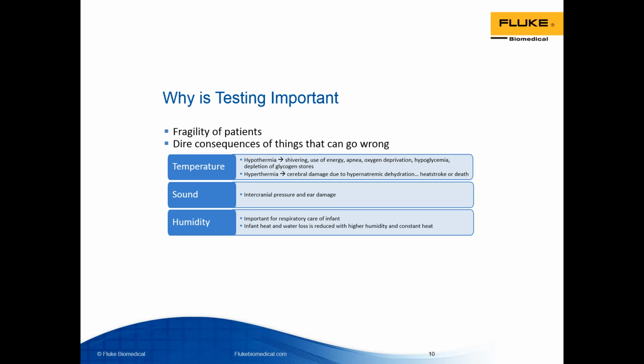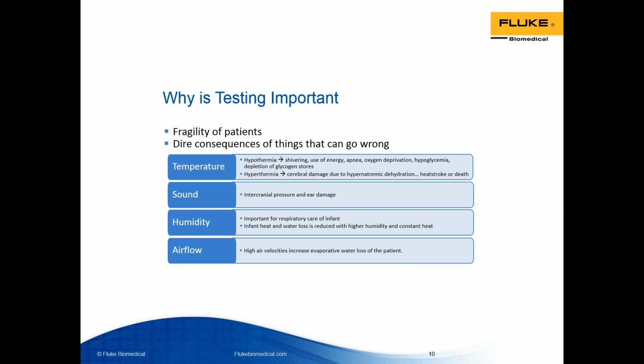Humidity is extremely important for the respiratory care of the infant. So humid air is what helps the baby to breathe and for the oxygen to be exchanged into the blood and carbon dioxide out of the blood at the very cellular level. So when a higher humidity is set in the incubator along with a constant heat, the infant heat and water loss are reduced, which is very desirable. As for airflow, we talked about this, and airflow helps circulate the warm air throughout the cabin, but high air velocities, so anything above that 0.35 meters per second that we talked about, can often lead to evaporative water and heat loss for the patient.